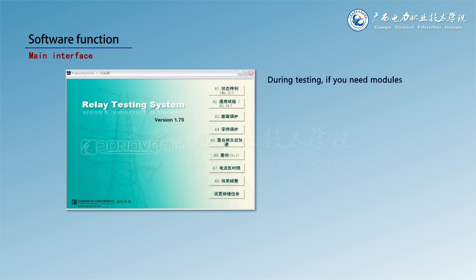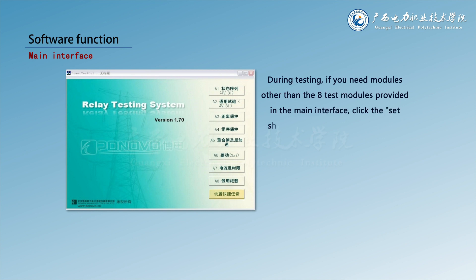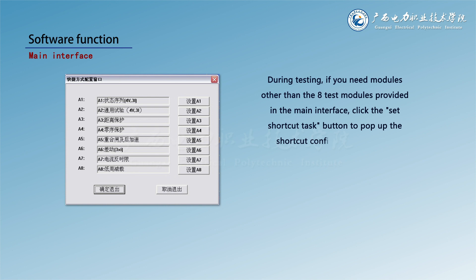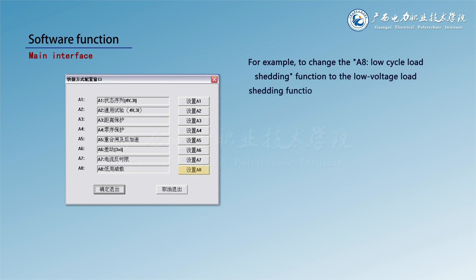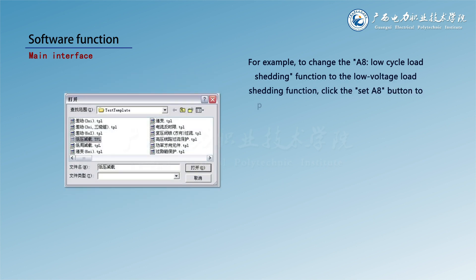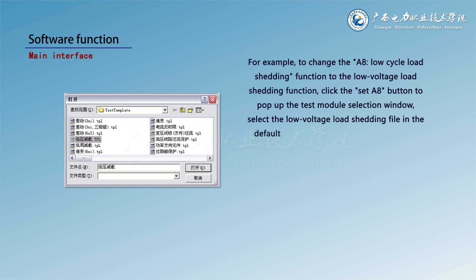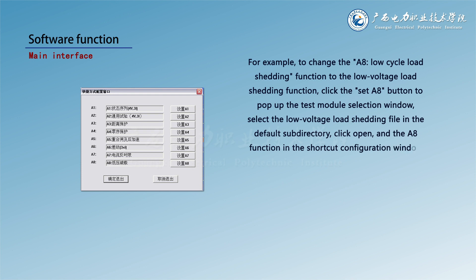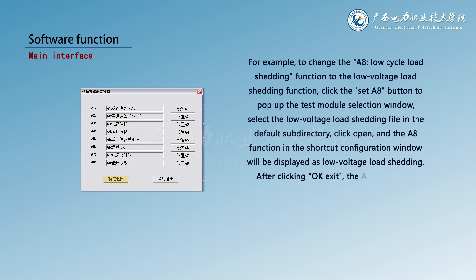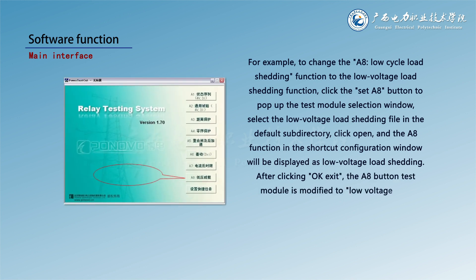During testing, if you need modules other than the eight test modules provided in the main interface, click the set shortcut task button to pop up the shortcut configuration window. For example, to change the A8 low cycle load shedding function to the low voltage load shedding function, click the set A8 button to pop up the test module selection window. Select the low voltage load shedding file in the default subdirectory, click open, and the A8 function in the shortcut configuration window will be displayed as low voltage load shedding. After clicking OK to exit, the A8 button test module is modified to low voltage load shedding.